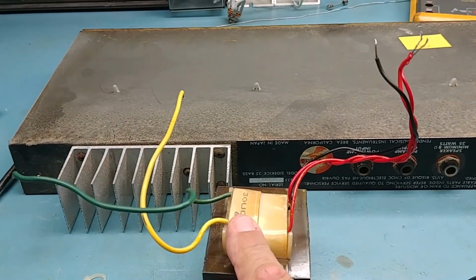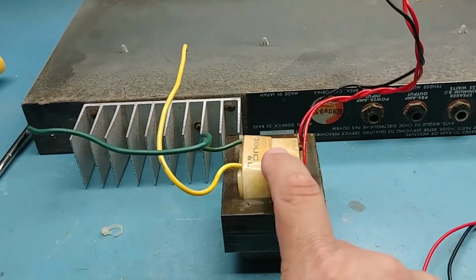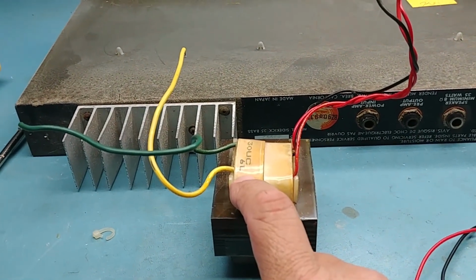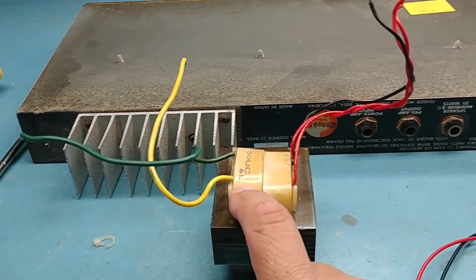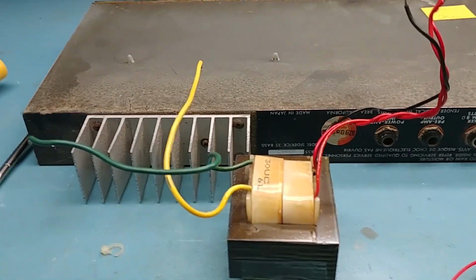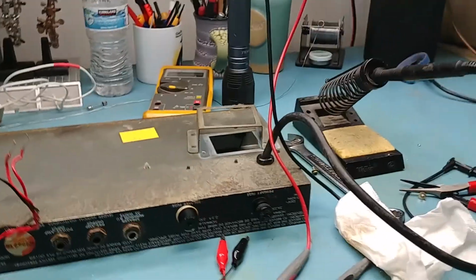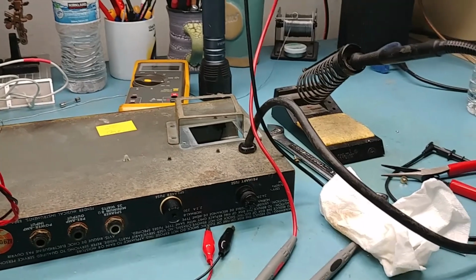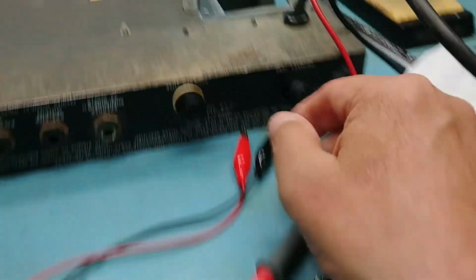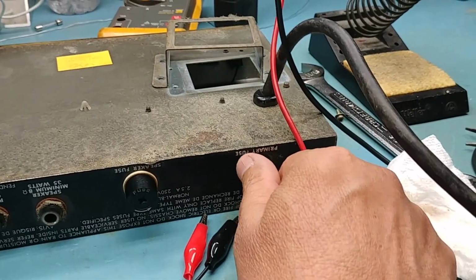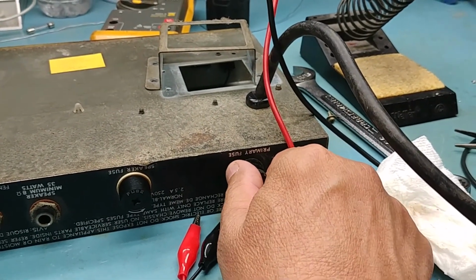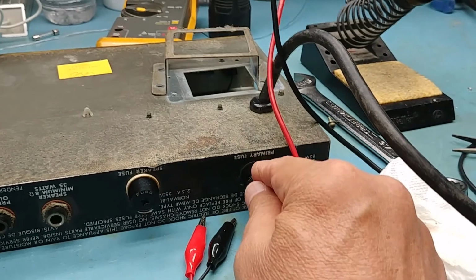So what could cause this? Okay, so like I said, it could just be an issue with this transformer. It could have just burned up because it's a low quality transformer. That's very possible. Another thing could have been that we got some surge current or surge voltage from the AC line that this was plugged into at one point. And if this mains fuse was overrated, then it's going to burn up the transformer before it pops this fuse.